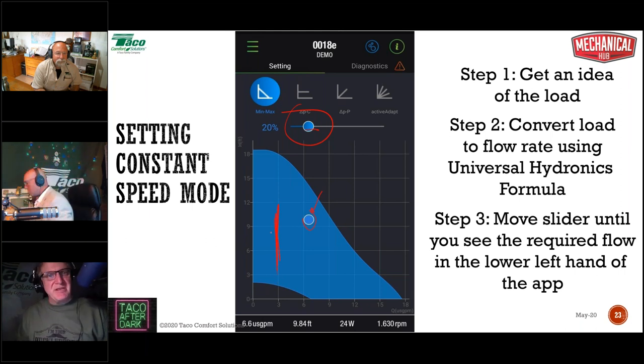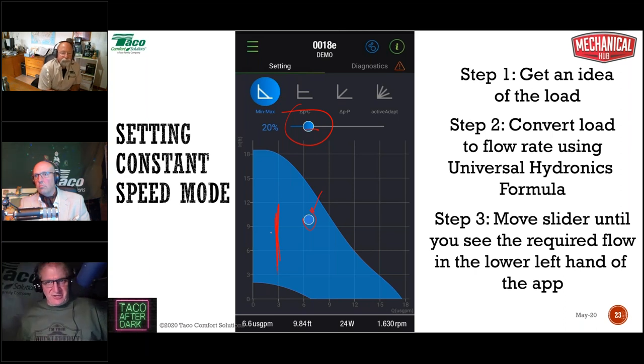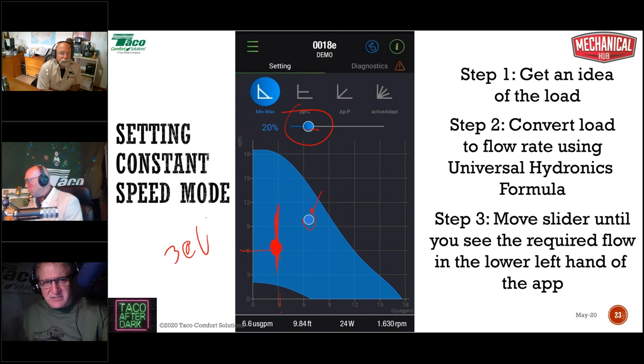The thing is, because it's working on the system curve, it's going to tell you the head loss. So you don't have to figure out the head loss. This will tell you the head loss at 3 gallons a minute. So let's say we move this slider and we intersect right about here. So what it's going to tell you is 3 gallons a minute at 6 feet of head. So it's 3 at 6. That's where it's going to work.